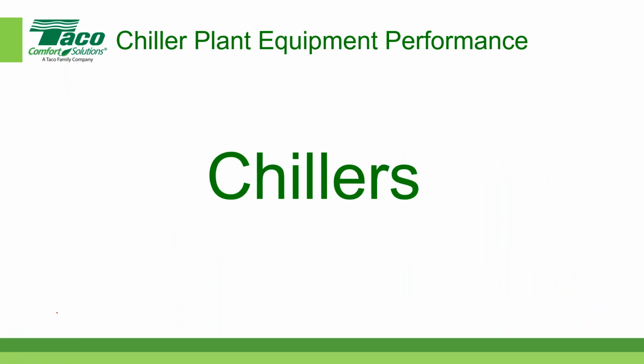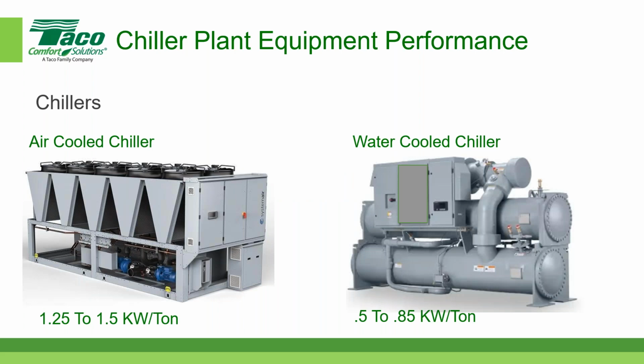So let's talk a little bit, like we said, about chillers. There are 2 major categories of chillers that are used in chiller plants today. The one on the left is an air-cooled chiller. The one on the right is a water-cooled chiller. What are some of the differences? Well, let's state the obvious. Air-cooled chillers reject their heat to the atmosphere. So this one here has fans at the top. It draws air into the condenser over here, I have some arrows for drawing the air in, and it exits out the top using these propeller fans. That's how most air-cooled chillers work.